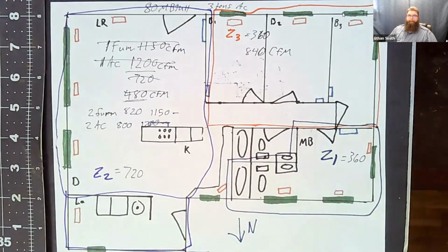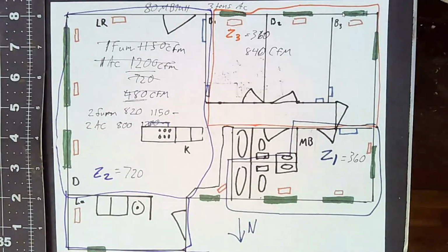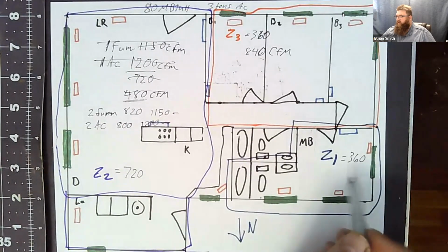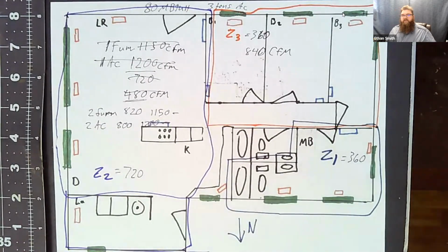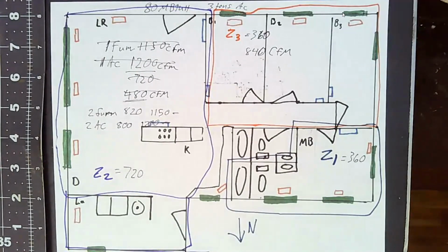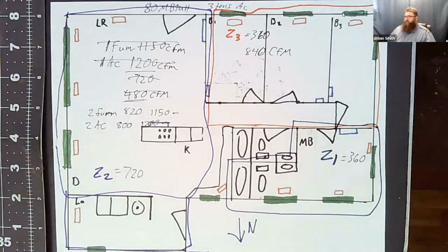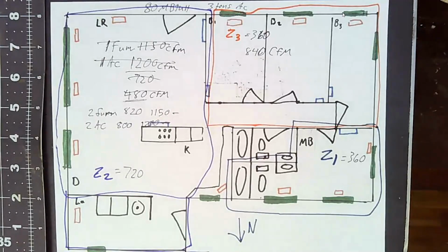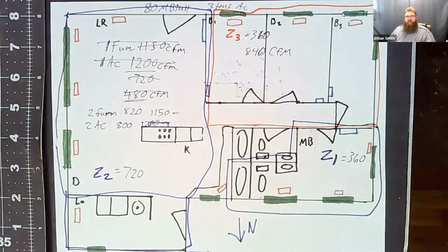And if so, why? Yes, because you can put it in low stage in the lower zones, the lower capacity zones. Okay. Do you think I could run it in low stage with just a 360 CFM zone? Yes. Okay. We'd have to do something with our excess air. With modulating zoning, you could just open up a little damper and let some relief out. Okay. So we'd have to use some type of relief strategy, whether it's a relief, bypass, a dump, something. We could probably make that work.